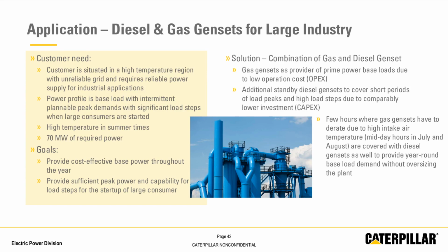Yes, Malta. So the solution was to use the correct combination of both gas gensets and diesel gensets. For the low operation cost, or the OPEX, the gas gensets were installed for the prime power base load. Then for the short periods of peak loads and high load steps, standby diesel gensets were the answer, with the comparably lower investment, the CAPEX, versus gas. Also, in addition to the peak loads and high load steps, the diesels were needed then for periods of hot weather to maintain even the base load demands.